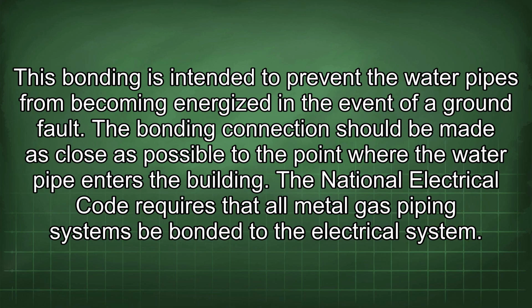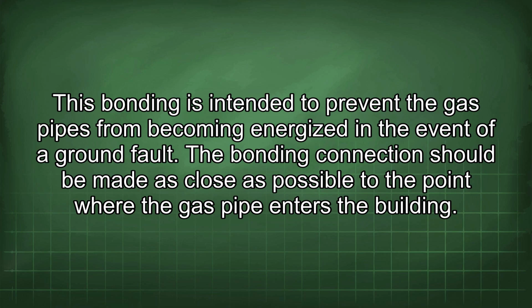The National Electrical Code requires that all metal gas piping systems be bonded to the electrical system. This bonding is intended to prevent the gas pipes from becoming energized in the event of a ground fault. The bonding connection should be made as close as possible to the point where the gas pipe enters the building.